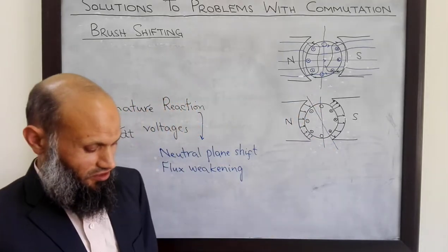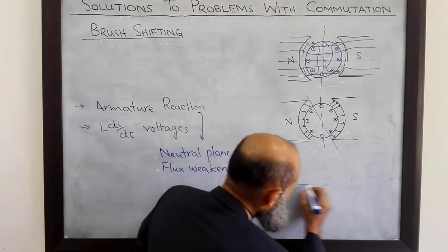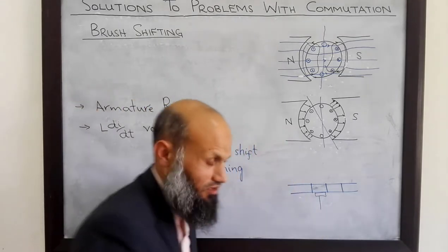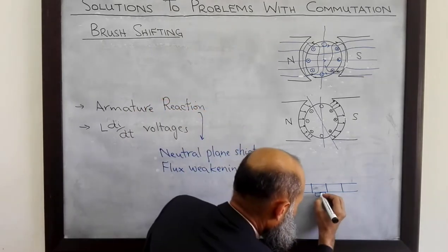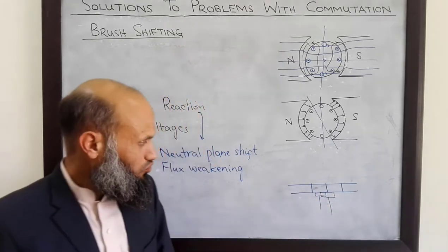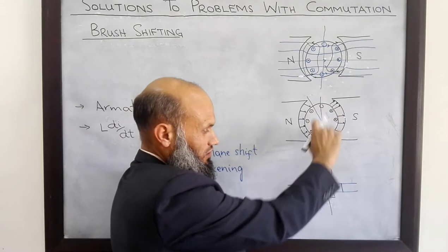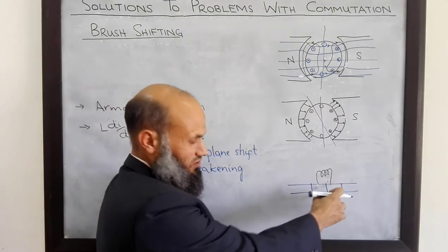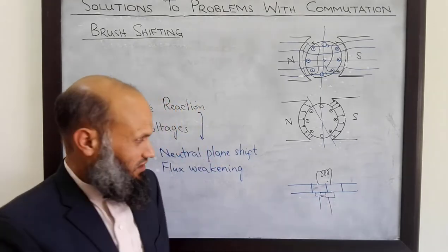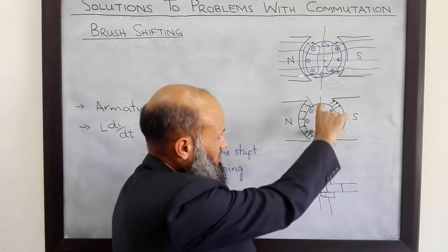What is the consequence of this neutral plane shift? We know that the commutator is on the rotor and is rotating. Commutator segments are also rotating. There is a time instant when a brush moves from one location to a new location, and at that time instant, two commutator segments are shorted through this brush. There is a coil connected to these two commutator segments, and each coil behaves as a voltage source. If two ends of a voltage source are shorted, that will be problematic. However, brushes are placed such that the shorted coils will have zero voltage induced — that is, the coil being shorted lies on the neutral plane.